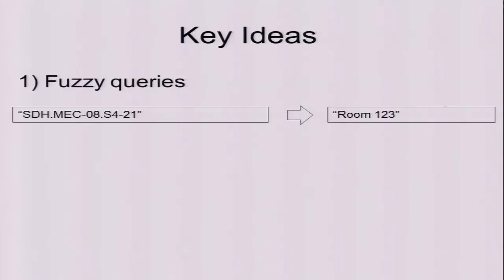There are basically two key ideas here. One is that we need to move away from arcane names and hard-coded control based on things like S421, and start talking at a higher level, like controlling something for a particular room or floor, or changing the temperature for all window-facing offices on the top floor of the building. That kind of logic can be applied from building to building and still retain its meaning.